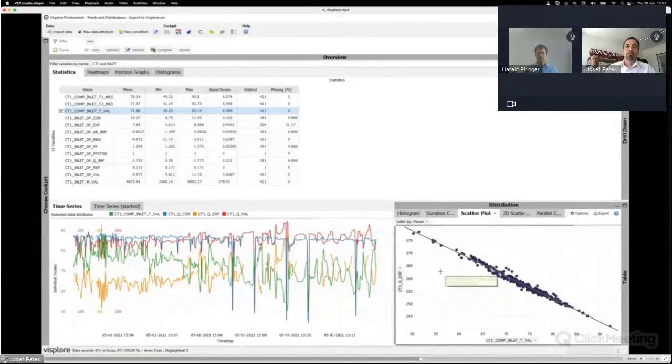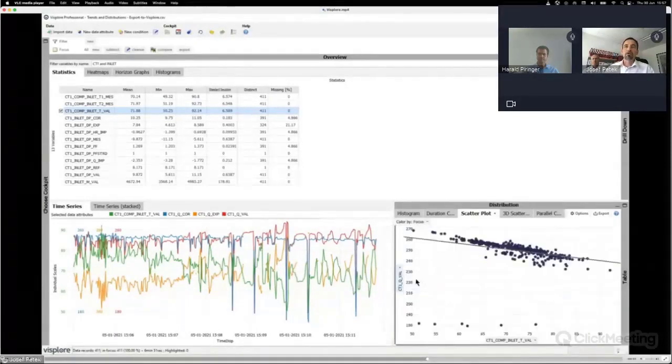So we look further. The next KPI we see here is the expected power output, which is the direct model result. Expected shows a quite clear correlation to ambient temperature, and this is the actual power. Again, we see correlation for the majority of data points, but some data points that fall off the expected behavior.